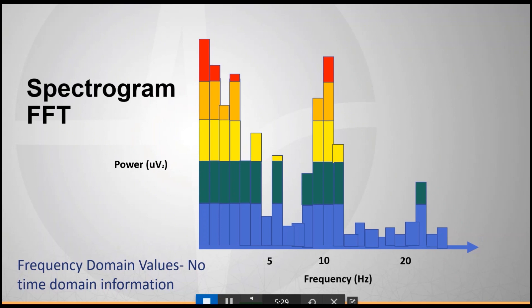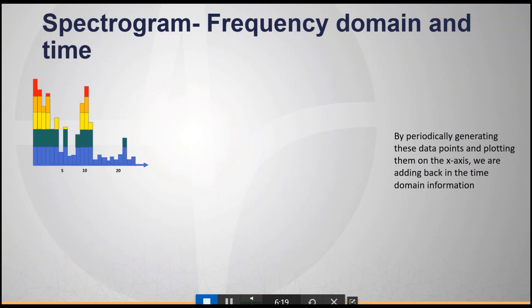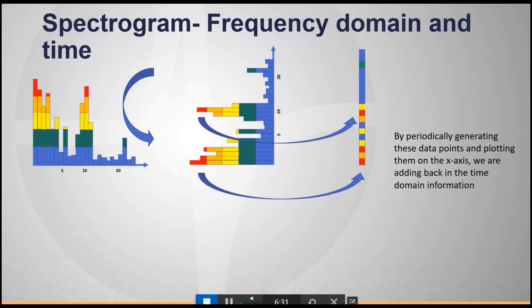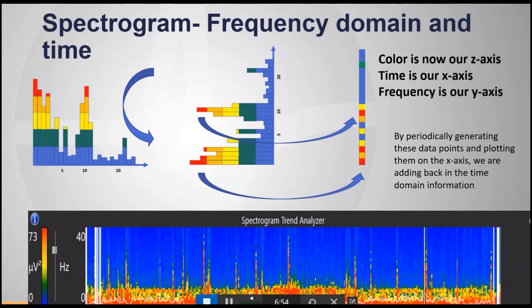The spectrogram is one of the most often used — it may be called the DSA or Density Spectral Array in other programs — and it's composed of multiple frequency spectra. The spectrogram takes the frequency spectra and color-codes each frequency segment based on the power of that frequency. We take each frequency spectra, flip them over, turn them around, and stack them next to each other. In the spectrogram, the y-axis is frequency, the x-axis is time, and the z-axis is power, represented by colors on the color scale.